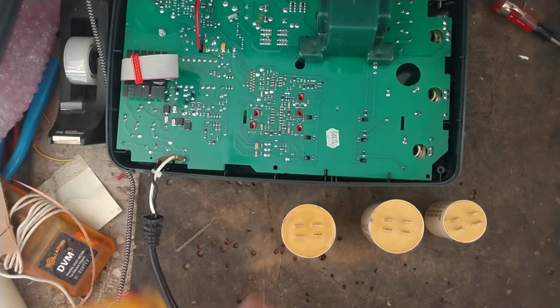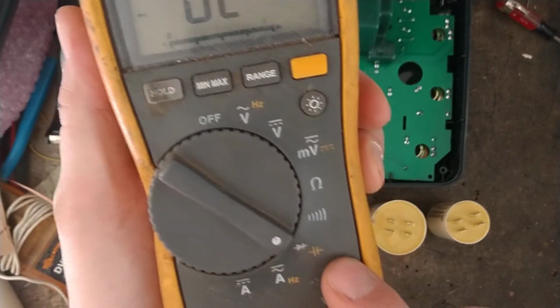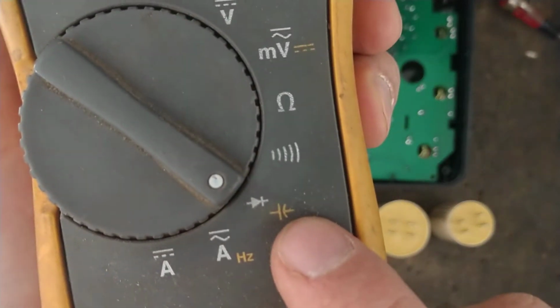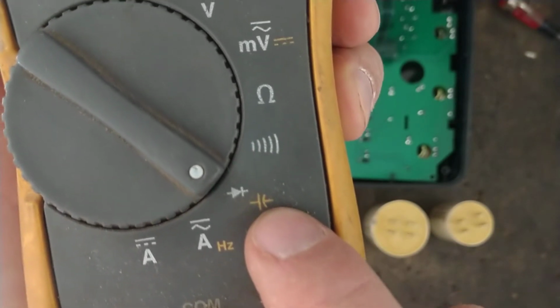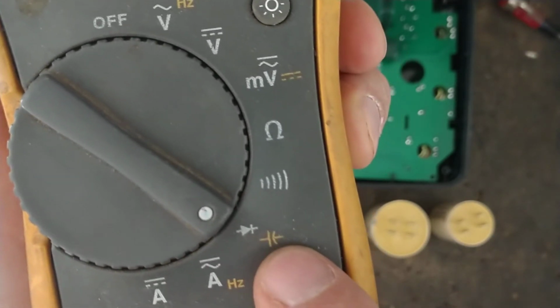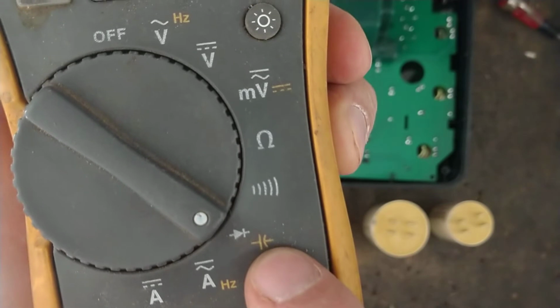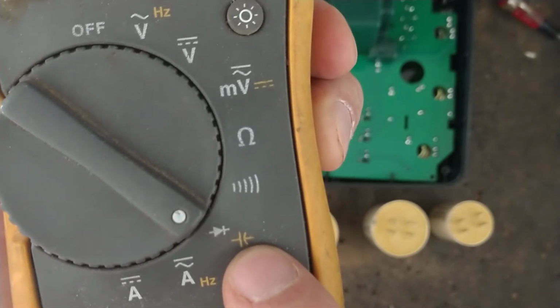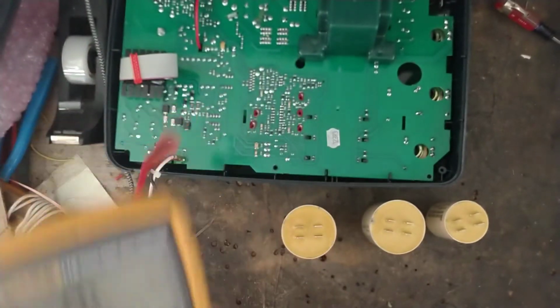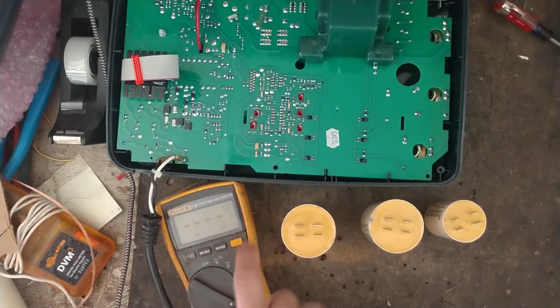To test your capacitors, look at your meter for that yellow symbol, not the white one, but the yellow one. That's the symbol for a capacitor. If your meter doesn't have that, it can't test these type of capacitors correctly. We use a Fluke 115, that's the meter we use.